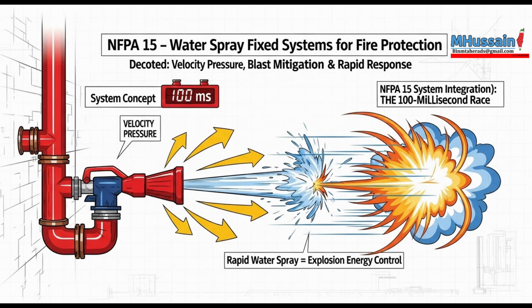That's 7.4.2.1. But critically, NFPA 15 tells you why that number. Ah, the assumption behind it. Exactly. Annex A.7.4.2 states this rate is specifically calculated based on an assumed heat absorption rate of 20,000 BTU per hour per square foot. That transparency is great, so the engineer knows exactly the heat load their system is designed against. If their analysis shows a worse fire scenario, potentially exceeding that 20,000 BTU rate, then the standard forces them to use a higher water application density. They have to compensate.